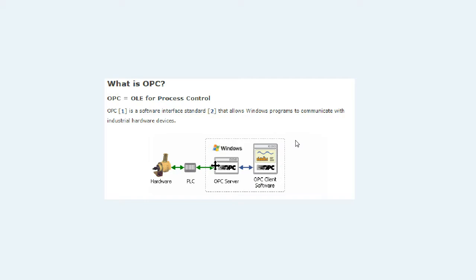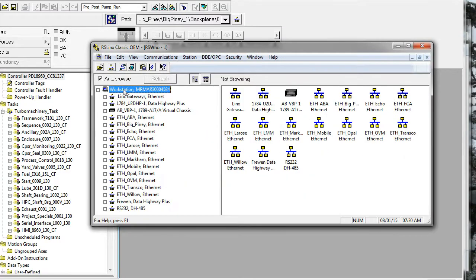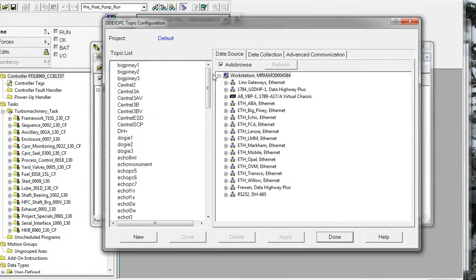Let's go through an example of setting up RSLinx to connect to a PLC. I have RSLinx open here, and you're probably used to browsing the connections you've established in your configuration. Here's where you would configure your connections, and here are all the different connections I have configured. When you set up an OPC server, you have to provide paths to the PLCs, and those are called topics in RSLinx speak. This is done through the menu item DDE/OPC topic configuration.